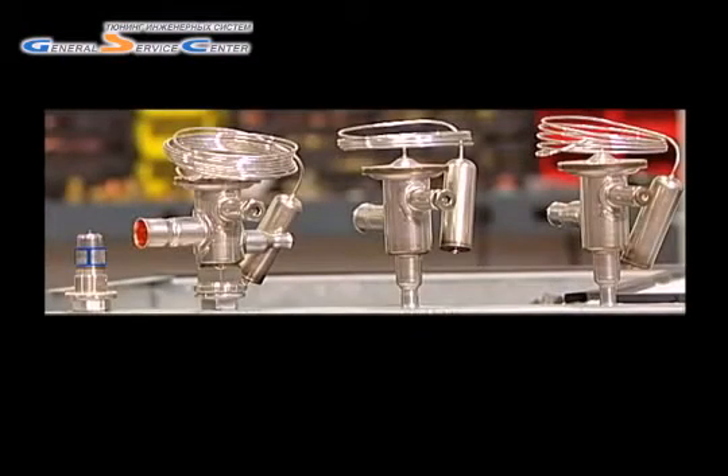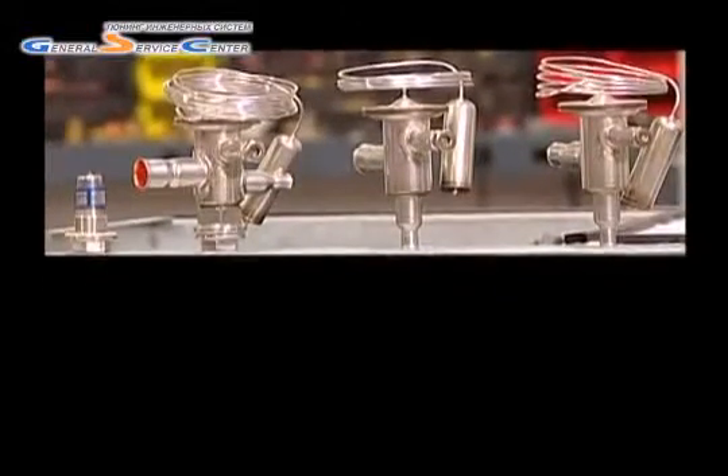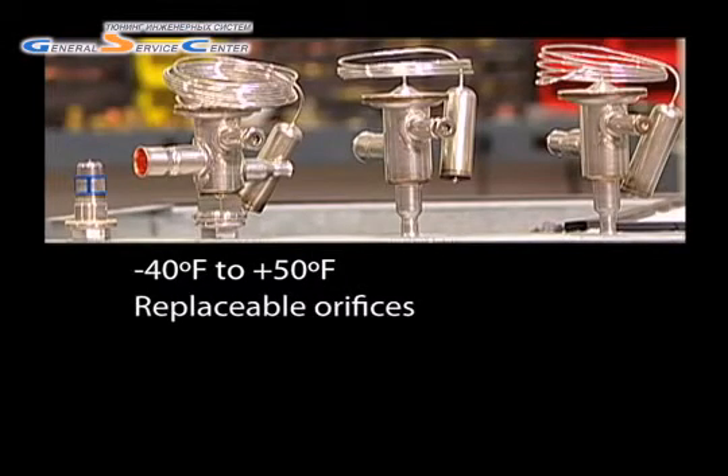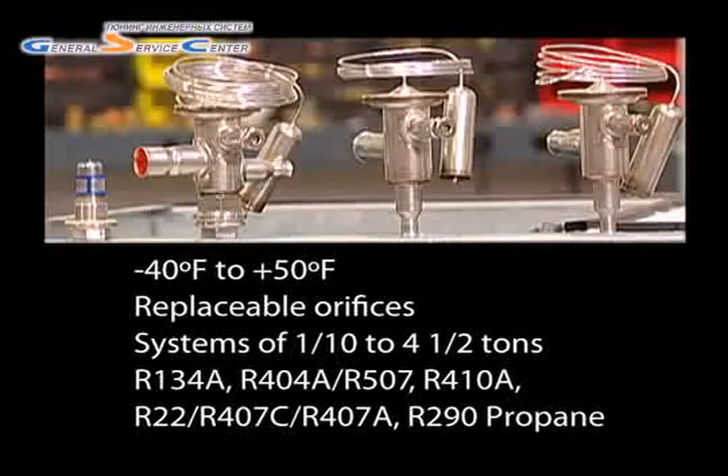Although the valve can be equipped with a variety of charges, the most common — the N charge — is designed to function in a temperature range from minus 40 degrees Fahrenheit to plus 50 degrees Fahrenheit.